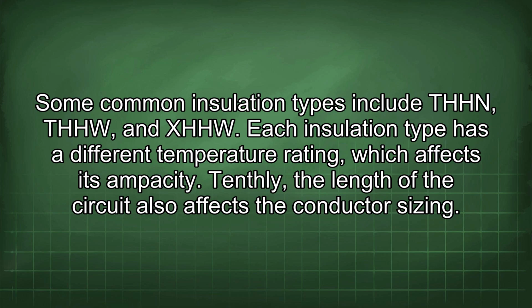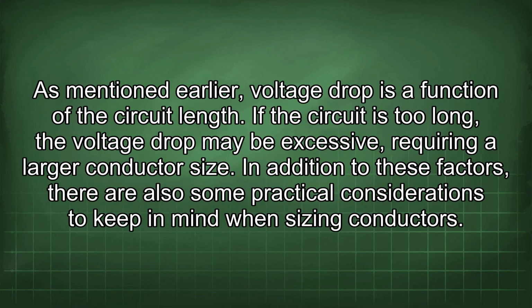Tenthly, the length of the circuit also affects the conductor sizing. As mentioned earlier, voltage drop is a function of the circuit length. If the circuit is too long, the voltage drop may be excessive, requiring a larger conductor size.